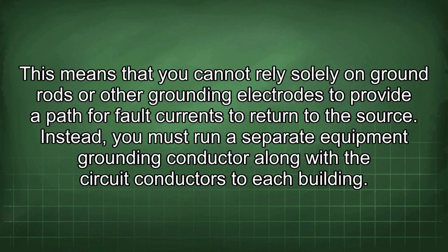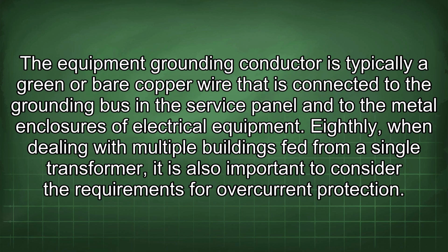Instead, you must run a separate equipment grounding conductor along with the circuit conductors to each building. The equipment grounding conductor is typically a green or bare copper wire that is connected to the grounding bus in the service panel and to the metal enclosures of electrical equipment.